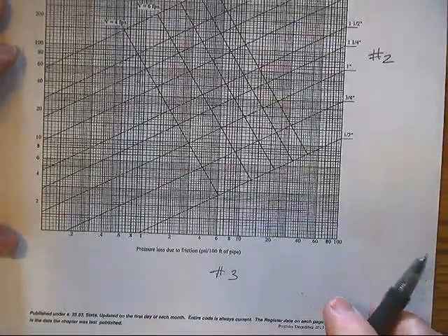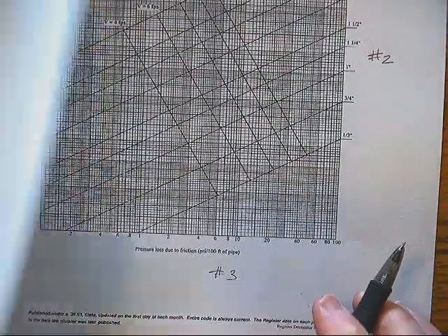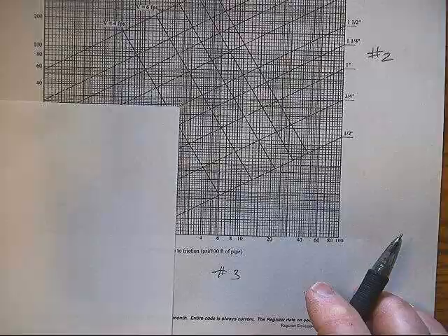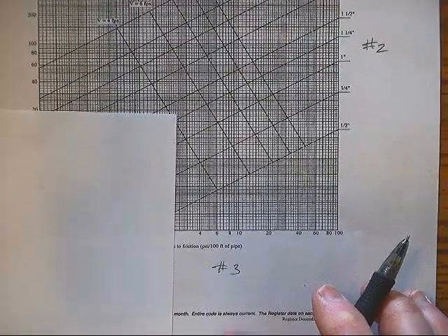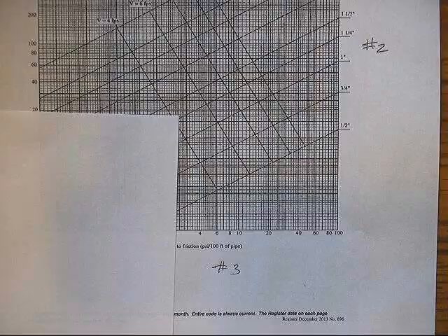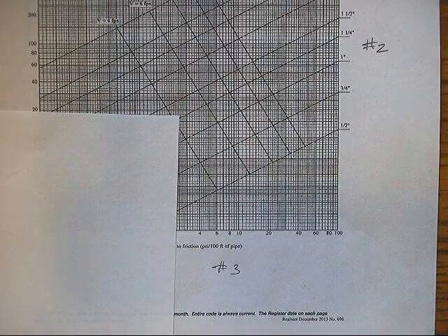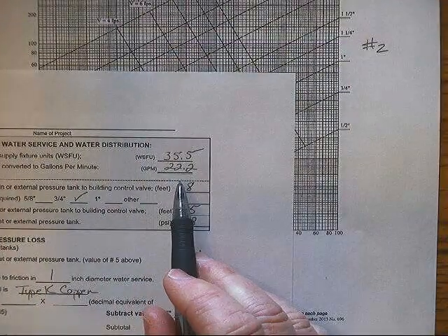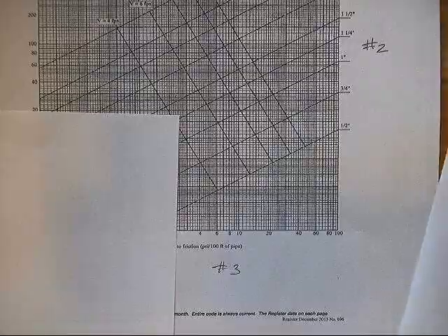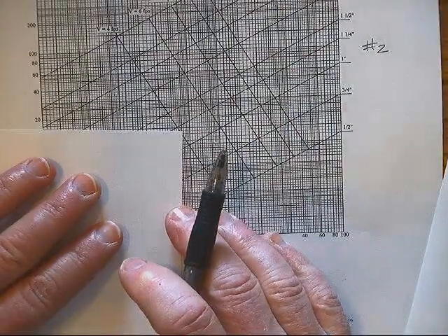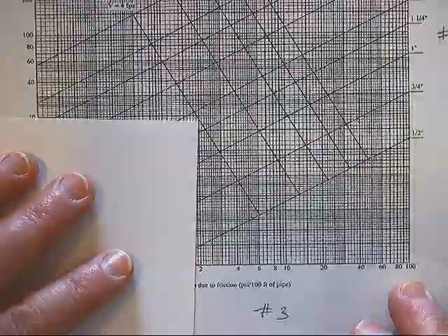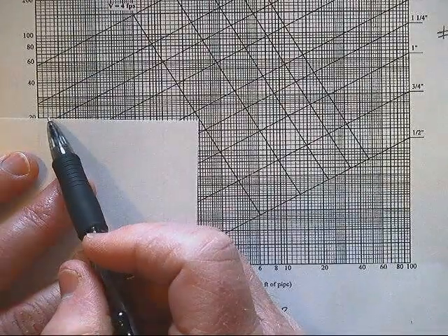So the easiest way to use these graphs, I've found, is to use a sheet of paper and a right angle, and we will do our best to read through the graph as close as possible to the actual gallons per minute that we have for our project. Now, as you recall, we were at 22.2 gallons per minute. So we're going to do our best to find 22.2. I'm going to zoom in a little bit for you, and we're going to go to 20, and then we're going to determine what's going on here with our breakdown.